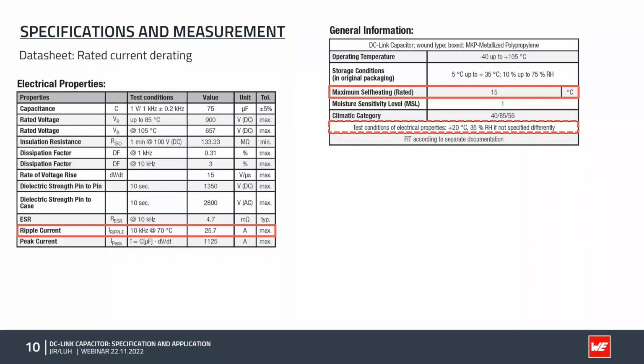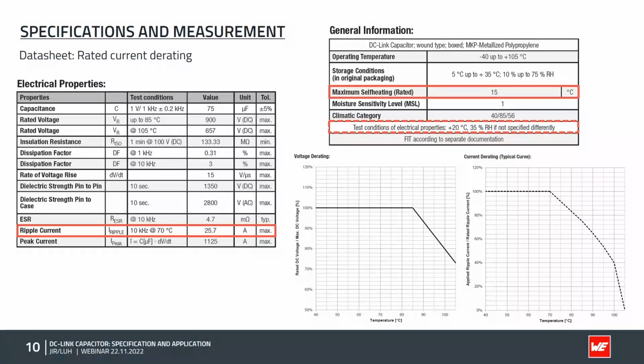So for more information, we add these temperature derating diagrams in the datasheet. As you can see on the left, the voltage rating applies up to 85 degrees Celsius; this is the maximum rated voltage. On the right, you can see the current rating applies up to 70 degrees, like in the specification. From this point on, the self-heating will be taken into account and derating is necessary.